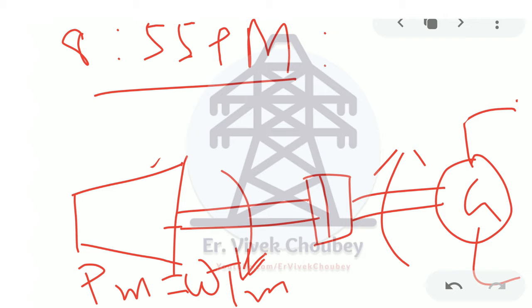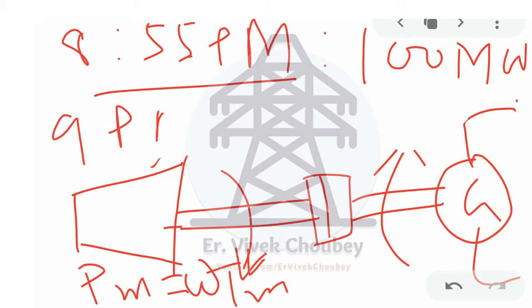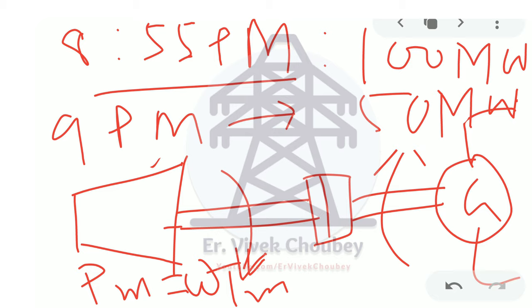The problem here comes if, let's say, the whole scenario was unknown. At 8:55 p.m., let's say we don't know that any such thing is happening, or the power system operators don't have any idea what is there. At 8:55 p.m., we are saying that, let's say, there is a demand of 100 megawatt. Okay, ideally, this is just an example. So there is a demand of 100 megawatt, and all of a sudden at 9 p.m. we are seeing, because we don't know, that there is a sudden demand decrease, and the new demand is 50 megawatt.